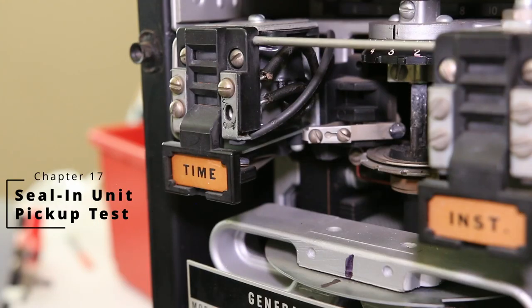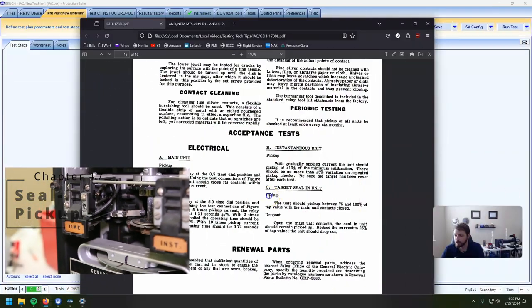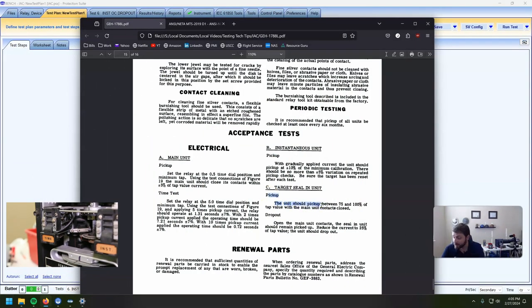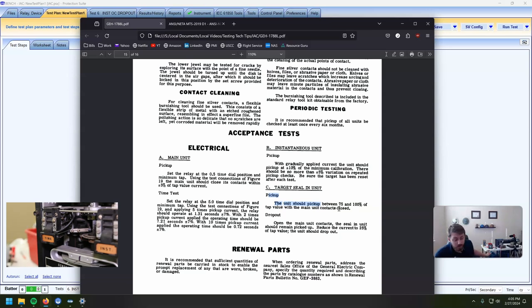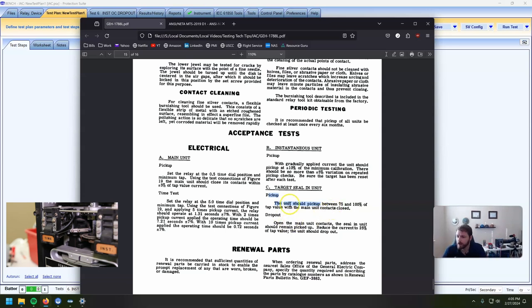The last thing we need to do is check the seal-in unit. The seal-in unit should pick up between 75 and 100 percent of the tap value with the main contacts closed. Ours is set to two amps — the other option is 0.2. The pickup should be between 75 and 100 percent of the tap value, which is two amps, and it should drop out at 25%. This is in series with the main trip contact — between terminals one and two for my induction unit.